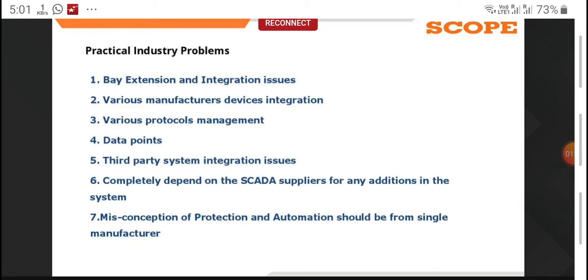Say one OEM has installed the complete automation system and protection system and erected the substation. One OEM has done everything, and after 5 years a bay extension comes. These extension bays are required to integrate with the existing SCADA system. Most people face issues there, because you have to purchase the existing OEM's BCU or relays so that they can easily integrate with the SCADA system.